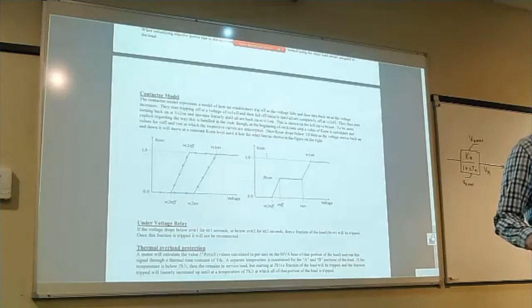Dimitri, you're not usually in the room for me to ask - this is the ice cube thingy, right? It's just like a little under-voltage relay that's tripping things temporarily and letting them come back. That would also be the contactors - you have DC power contactors, so you use a supply to the control circuit to close the contactor. So if the voltage drops low enough, it just opens, but it'll try again every so many seconds to come back. It's a spring, right? So once you have enough voltage, it overcomes the spring tension. If voltage drops, the spring falls off and comes back, and then you've got to overcome that again - that's why there's a separation in it.